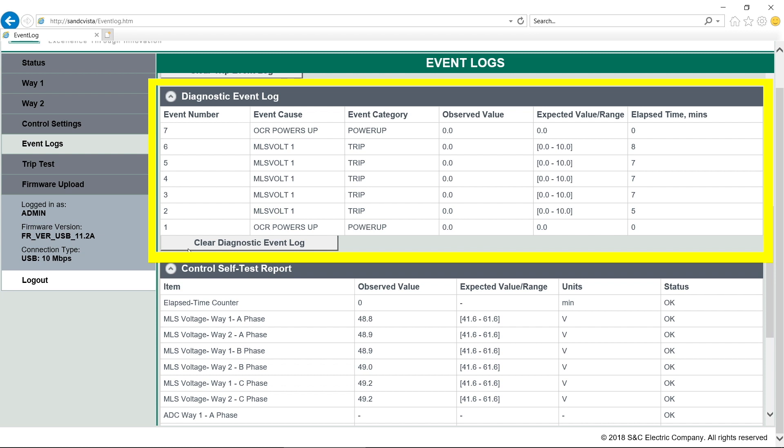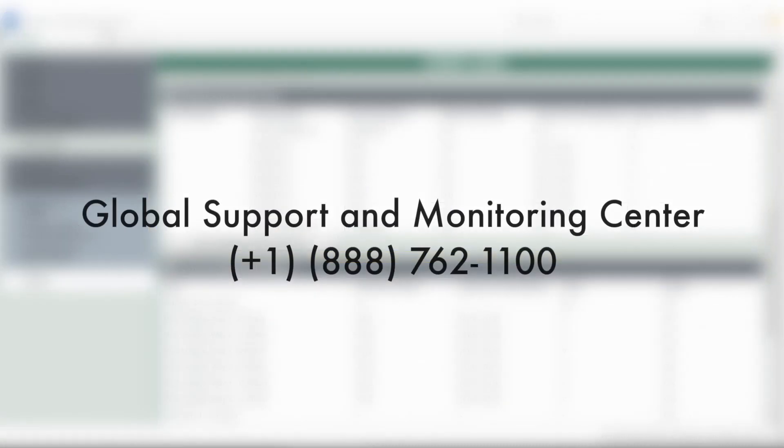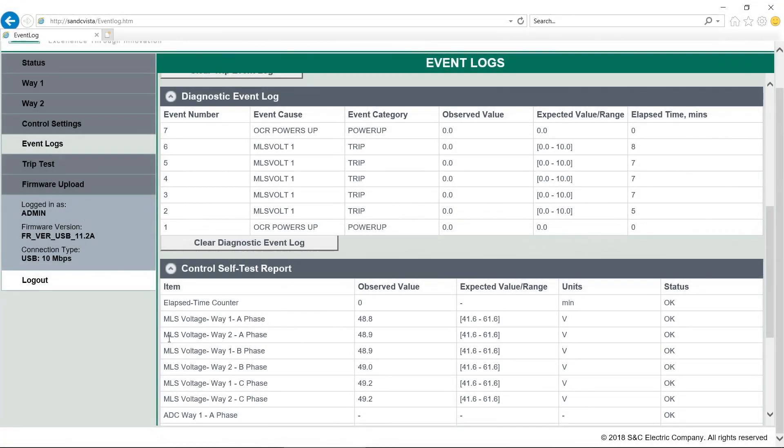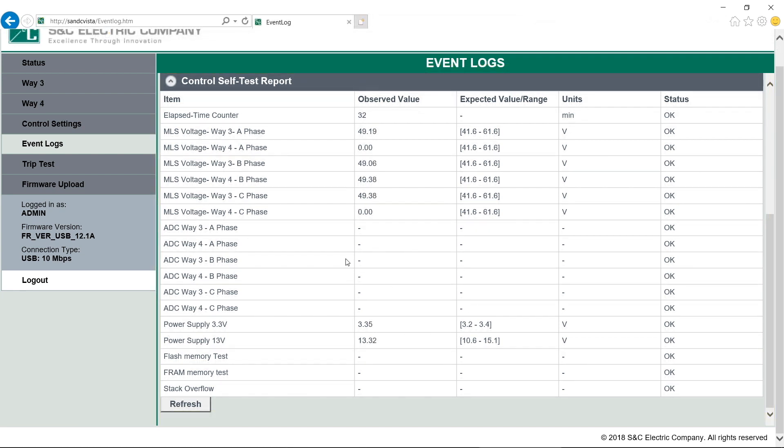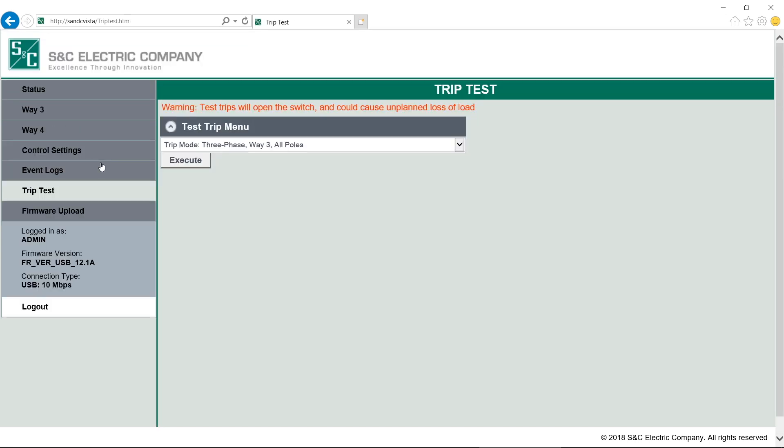The diagnostic event log shows the last 12 diagnostic events recorded by the overcurrent control. This is used mainly by S&C Electric Company to help troubleshoot any problems with the overcurrent control. You should report any error messages to S&C through the Global Support and Monitoring Center. Below that we find the control self-test report. The overcurrent control tests vital subsystems upon power-up and periodically during operation to ensure the control is working properly. This status field will show any errors or display OK after a test. Any errors should be reported to S&C. This is also used mainly by S&C in troubleshooting. Trip tests can only be performed under the admin login. Note that test tripping the overcurrent control will open the fault interrupter and may cause unplanned loss of load. See the written instructions before performing a test.